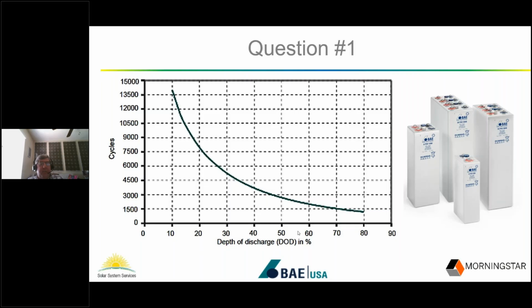The other thing, to your point, this is true: it's almost impossible to use 100% of any battery, as the voltage will collapse to the point at which your load would no longer function. There's some point at which your inverter is going to drop out, or whatever your load is, even a lighting load - it's going to not have the voltage to operate anymore, and it will stop long before you get to the end of discharge of your battery.